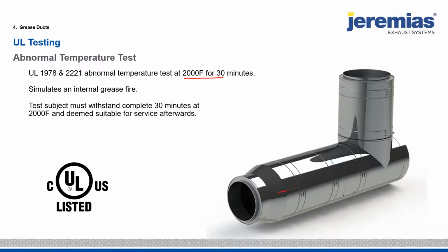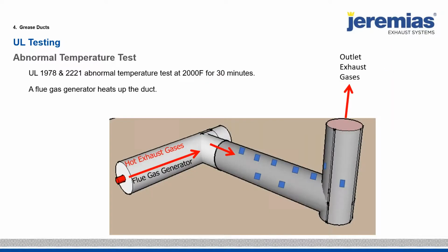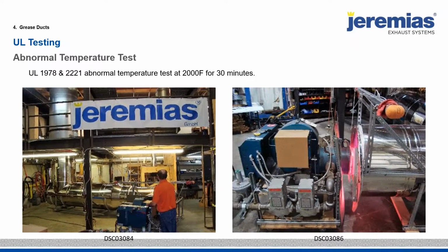We take a test subject that's about 15 feet horizontal, 10 feet vertical. We put a flue gas generator and we fire flue gases into this test subject. We're actually measuring skin temperatures with thermocouples to make sure that the clearance to combustibles is what we say is safe in our instructions. So that's the test setup. That's what it looks like right here. This is a 8 million BTU burner, and we're actually firing flue gases through this flue gas generator into the test subject. And I got some videos to show you.